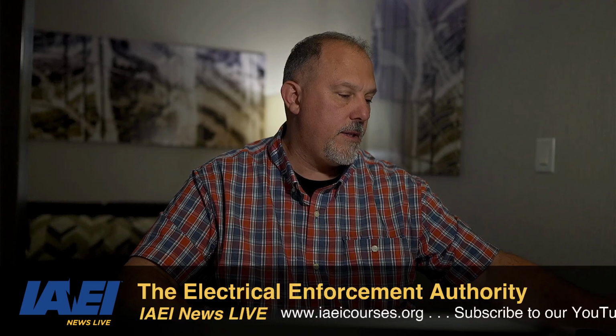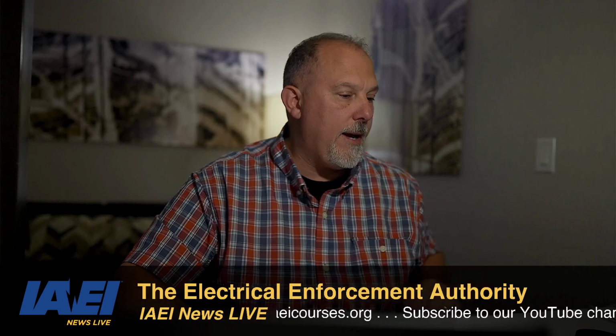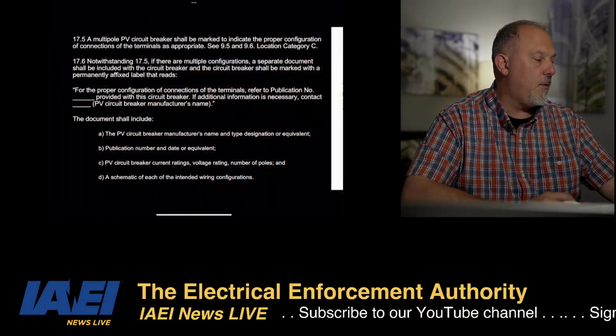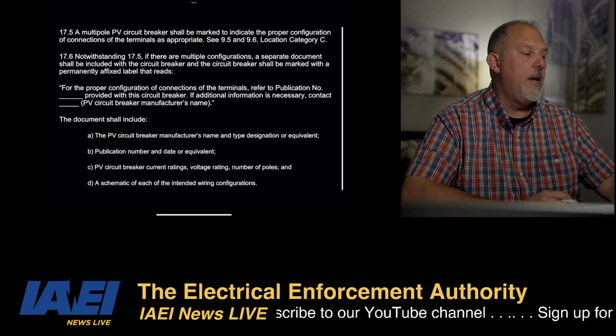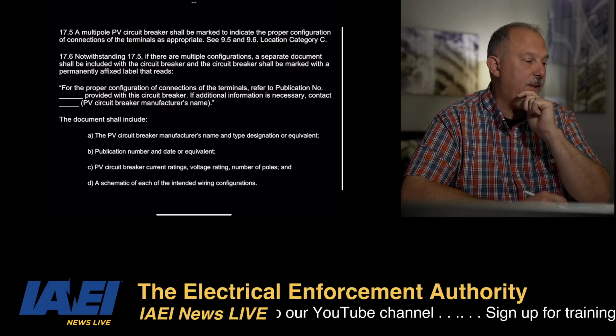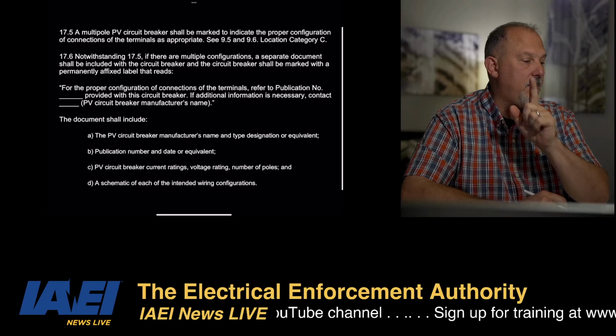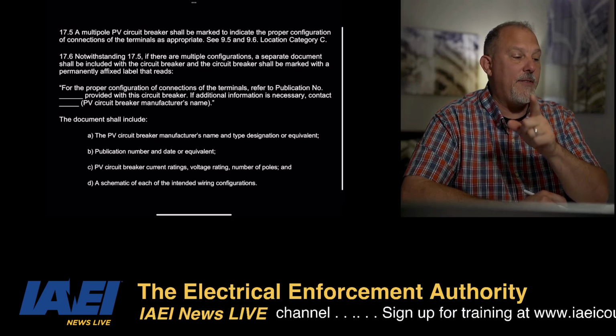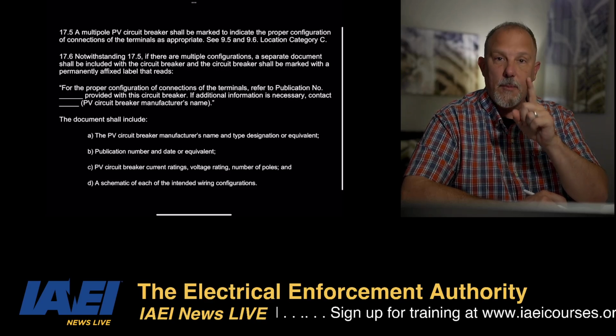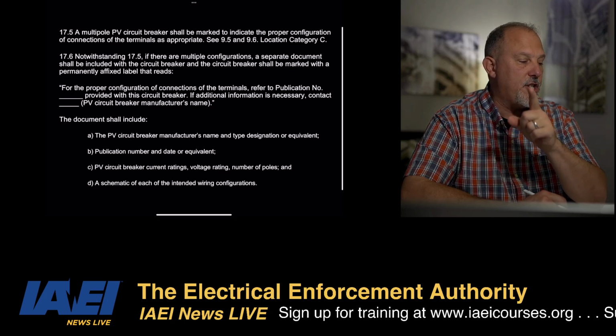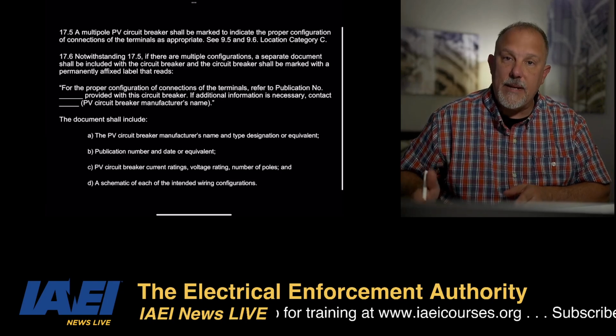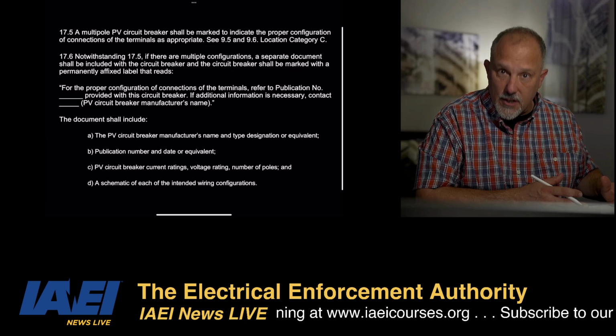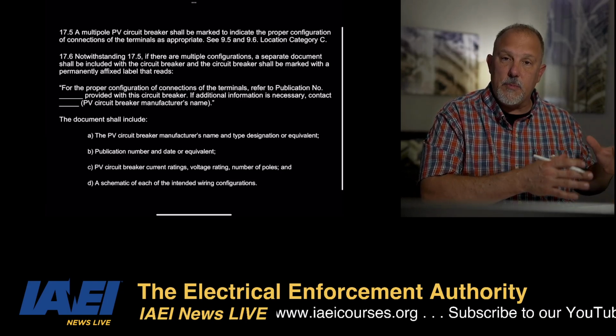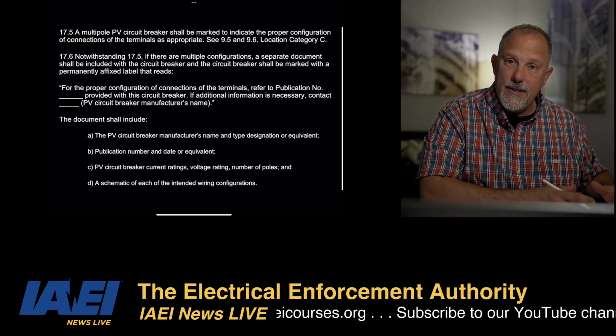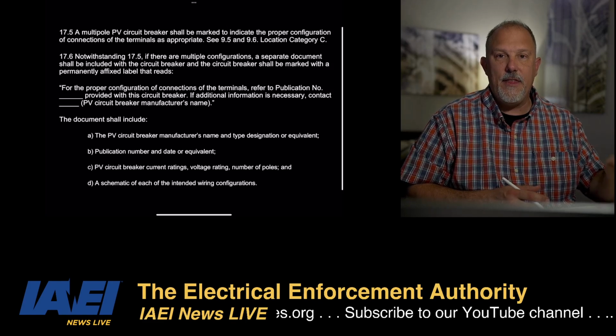Here's this. Yeah. Here we go. How about this one? Let's take a look at this one. This is for a multi-pole PV breaker shall be marked to indicate the proper configuration connections, notwithstanding 17.5. If there are multiple configurations, a separate document shall be included with the circuit breaker, and the circuit breaker shall be marked with a permanently affixed label that reads, for proper configuration of connections for the terminals, refer to publication number, blah, blah, blah, blah. So if you have a separate document that should be accompanying that circuit breaker to give you information on how it is supposed to be configured and wired, then you mark the breaker that information should be there.